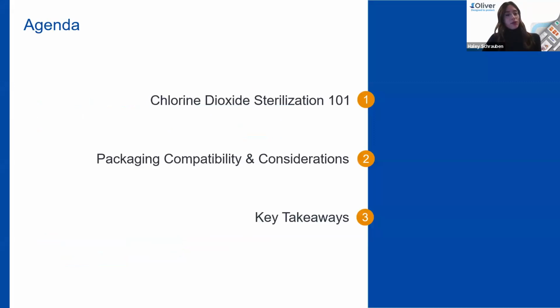Today's agenda will begin with an overview of chlorine dioxide sterilization, including what the gas is, the typical sterilization process cycle and validation, and its compatibility with medical devices. We'll then discuss chlorine dioxide sterilization compatibility with packaging materials specifically, including results from a recent aging study on several common sterile barrier system materials. And finally, we'll wrap things up with key takeaways.